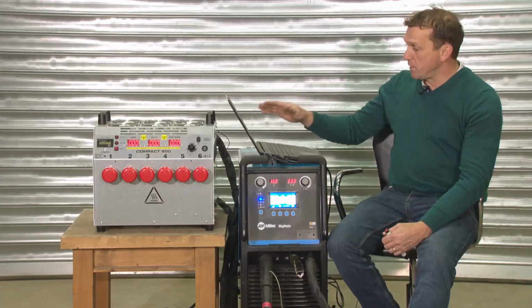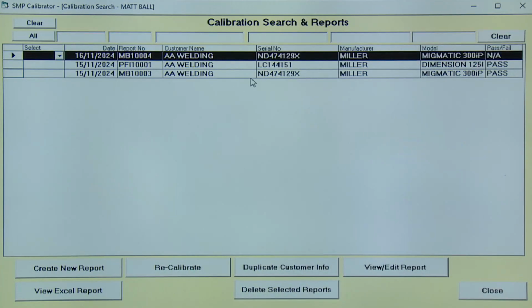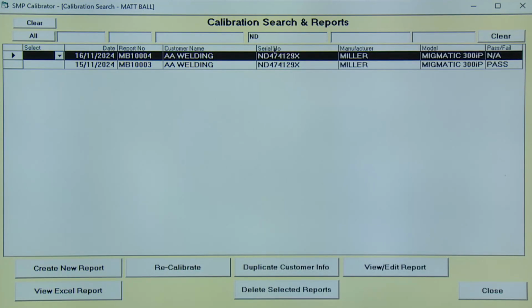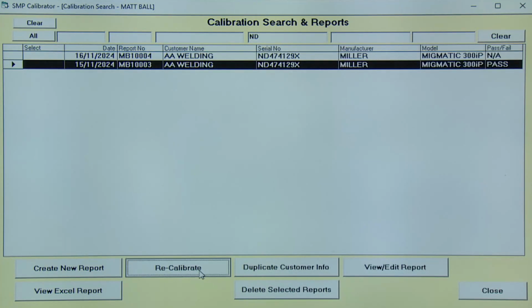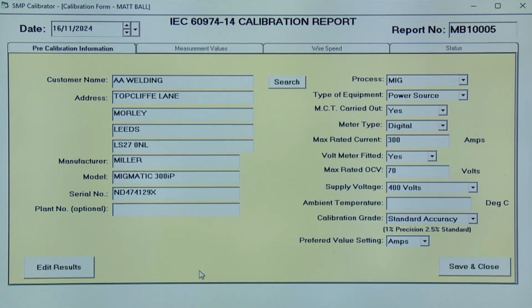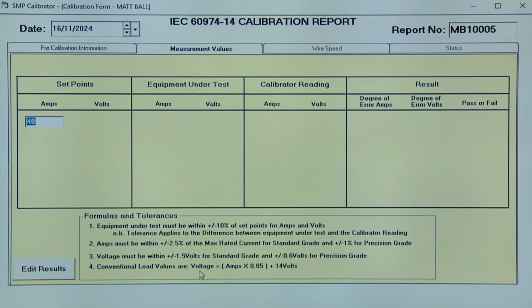Then we'll open a calibration form on the program. We've done this machine before, so it's quite easy to find, and hit recalibrate. All our parameters are in there, the process we're doing, maximum rated current and open circuit voltage. It's just the ambient temperature we'll need to change, 16 degrees today. If we hit start, it'll select our reasonable minimum, 40 amps for this MIG welder, and then our 5 evenly spaced readings across the range.